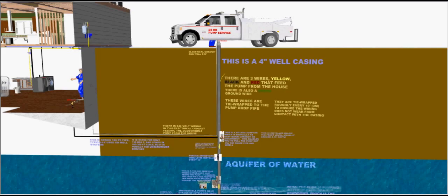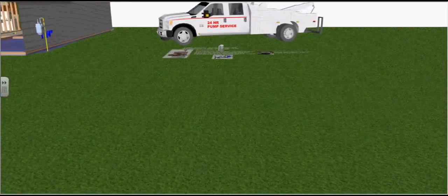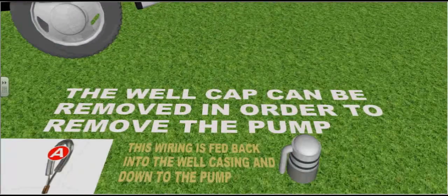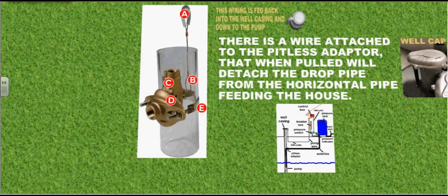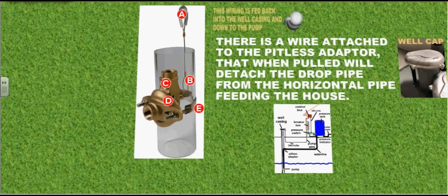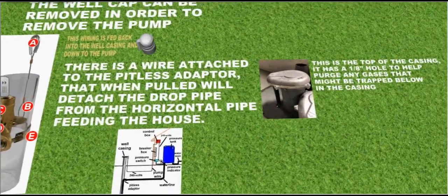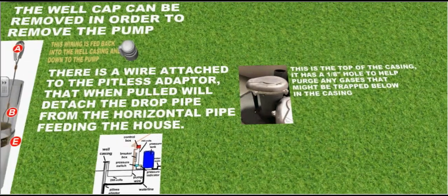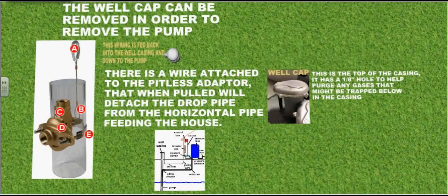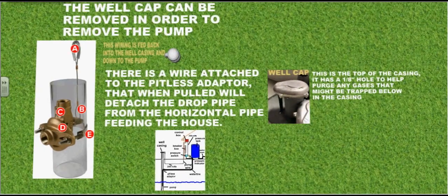This is a 4-inch well casing. The well cap can be removed in order to remove the pump. There is a wire attached to the pitless adapter that, when pulled, will detach the drop pipe from the horizontal pipe feeding the house. This is the top of the casing. It has a 1/8-inch hole to help purge any gases that might be trapped below in the well casing.